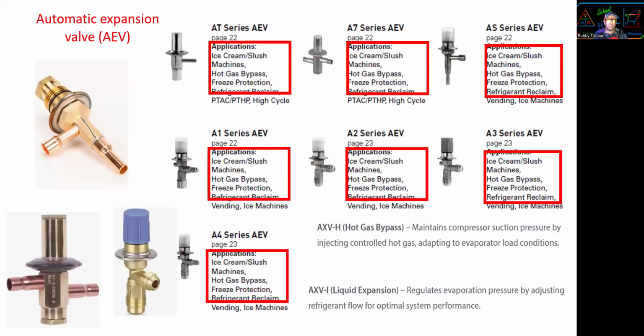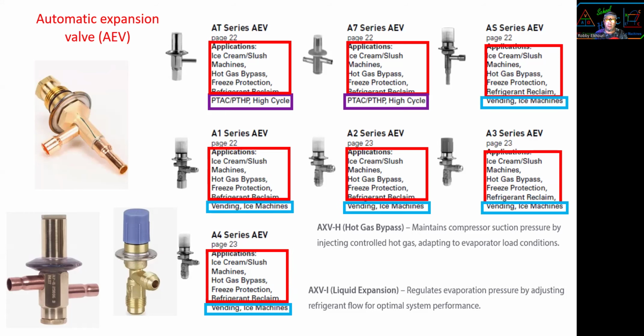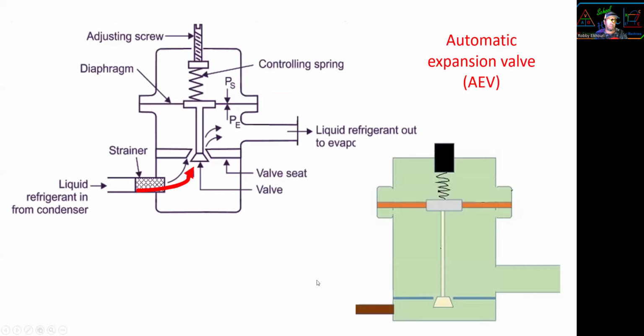We have most of them for ice cream, slush machines, hot gas bypass, that's freezers. Some are for PTAC, package terminal air conditioner, or package terminal heat pumps. And some for vending machines and ice machines, okay? And some are used for hot gas bypass, have nothing to do with metering device. All right, but most of them are used for liquid injection, which is metering device.